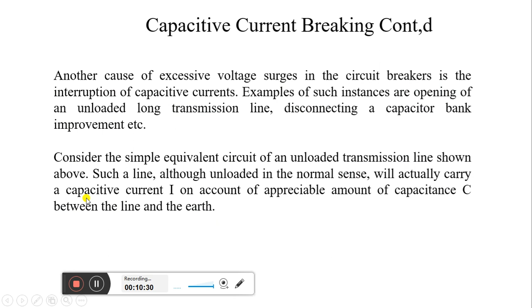Initially the maximum voltage Vgm was available. Now we are talking about half a cycle later, that is point R, where the potential of the circuit breaker contact A becomes maximum negative, which causes the voltage across the breaker VR to become 2Vgm. So at point R, A will have a negative Vgm. Earlier Vgm was available towards the B side, and now at the A side, minus Vgm is available at point R. So the difference of both voltages, Vgm and minus Vgm, will become 2Vgm.